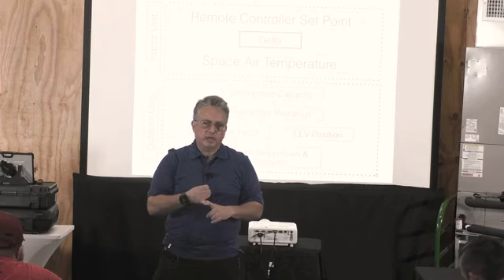You can have too much air coming in, too high a temperature, and the system is not going to respond well. Or if it's in part load, it may respond great in full load conditions, but in part load, it may not take care of the air treatment that you need.